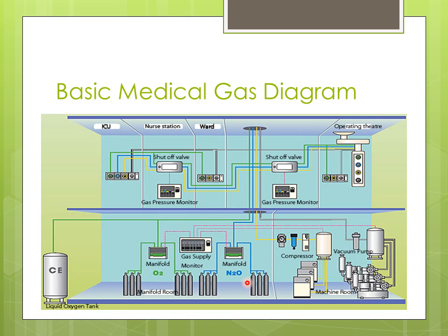Well, it almost certainly would have to be a rated room because, here's our wall. And when you have these tanks like this, all this has got to be a rated room. However, there's some things about this room which is interesting. One is that this gas monitor needs to be protected. I'm not so sure that I would put a gas monitor in the room with all the oxygen tanks. If there's going to be a fire or something like that, this whole thing's going to be engulfed, and this thing isn't really going to work. So I probably would have put this in a separate room.